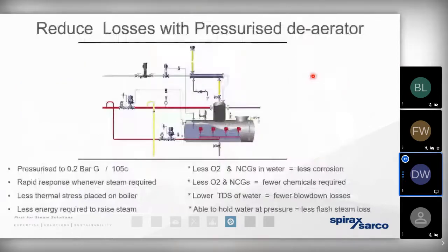And another area that we can give thought to, it's not exactly a new concept, but it is a concept that hasn't been widely utilized in the UK at the moment. It's what we refer to as a pressurized deaerator. So as we've mentioned, traditionally, we're going to keep that condensate that's returning from the process in a vented receiver or a hot well. And we can only keep that at atmospheric conditions where we know the maximum temperature is typically 85 degrees. But by pressurizing that vessel in a PDA, if we elevate the pressure to 0.2 bar gauge, it means we can now elevate the temperature of that feed water to around 105 degrees. And that's going to bring us a number of different benefits.